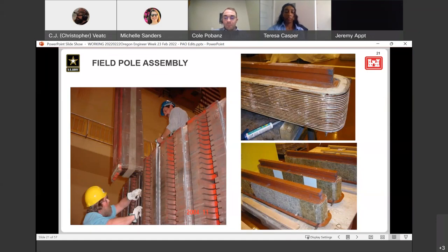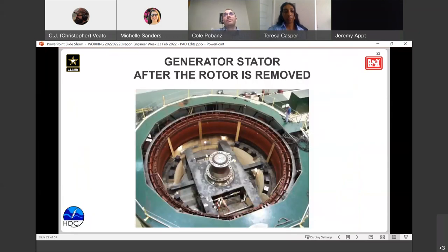When the generator is spinning, the exciter, which we'll cover later, sends the poles DC current. Thus the rotor poles are energized and turn into magnets when brought near other metal, entering the stator and its coils. Here's a picture of the stator with the rotor removed.